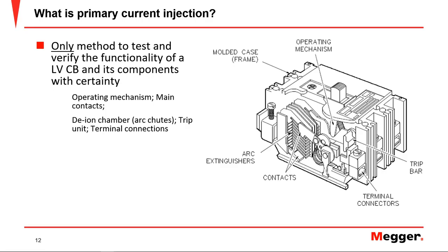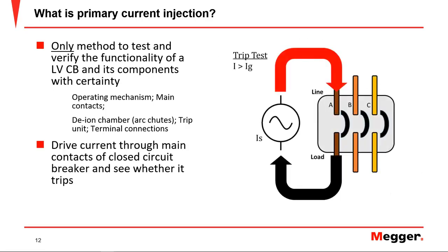And how do we do it? Well, as the name implies, we need a primary injection unit, a unit that will be capable of injecting current through the conductors of the circuit breaker. As you can see in the example diagram that I'm showing, we'll be testing pole by pole in the case of a three-phase circuit breaker. So we're going to inject current, and the name also tells us that we're going to be using current levels equal to those that we expect to see in the field, hence the name primary injection.